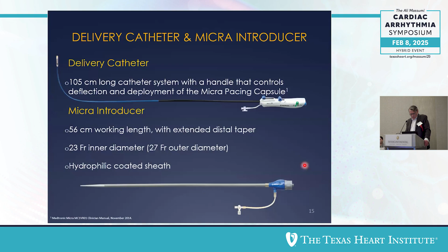Okay. All right, so the Medtronic version of this is a passive fixation. So it's got the nitinol fixation mechanism that is not in contact with where the cathode is in contact. You can see here on the left is just a typical active fixation electrode, and as you know, the fixation mechanism is the distal electrode. So what happens is you get fibrous tissue around where you interface with the myocardium from trauma from the screw. And of course, this leads to higher thresholds and reduced battery longevity.